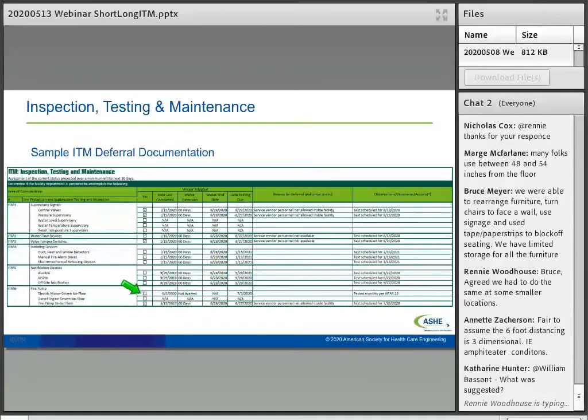Fire pump, electric motor drive, no flow conditions, this is a monthly requirement. Notice this was not waived by CMS, so facilities still have to continue doing this. That will continue just as noted the next month.